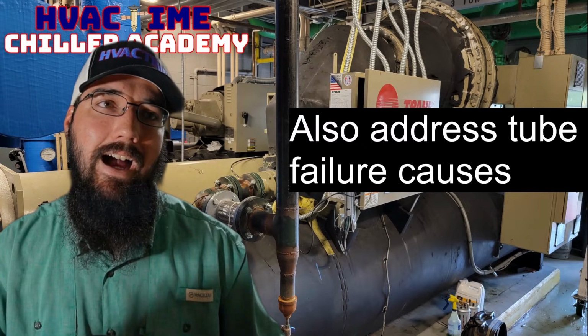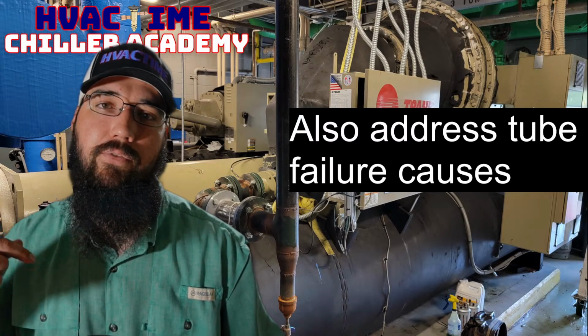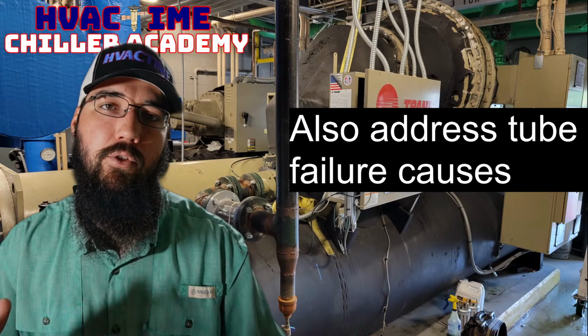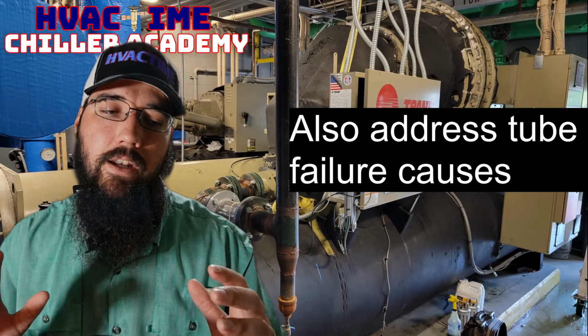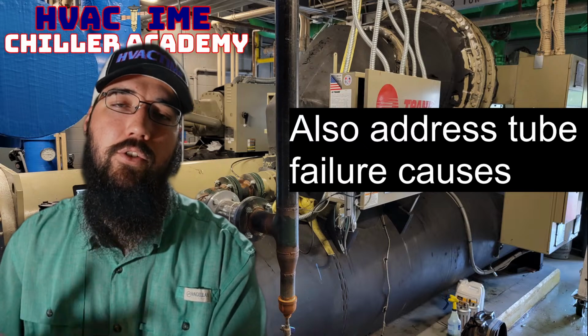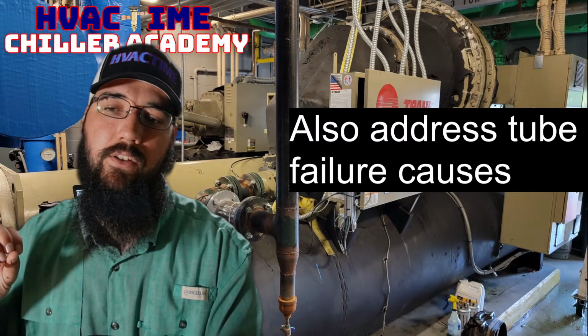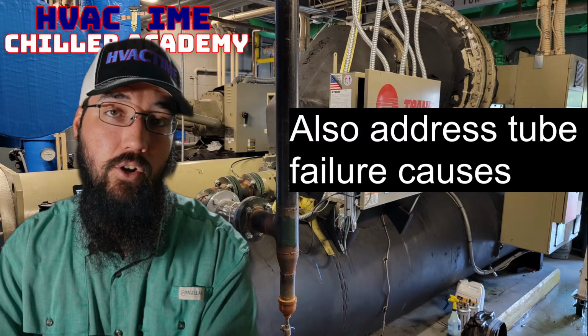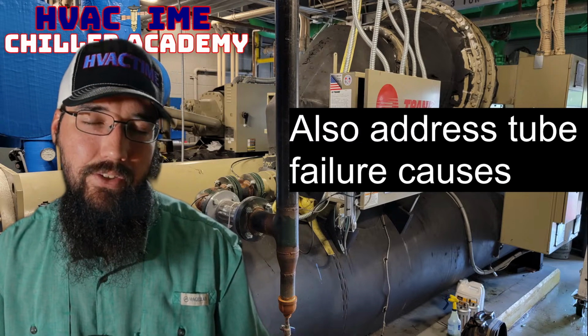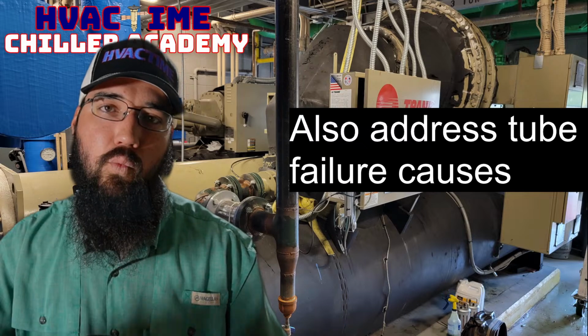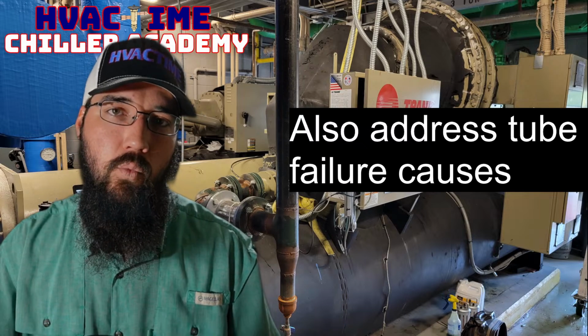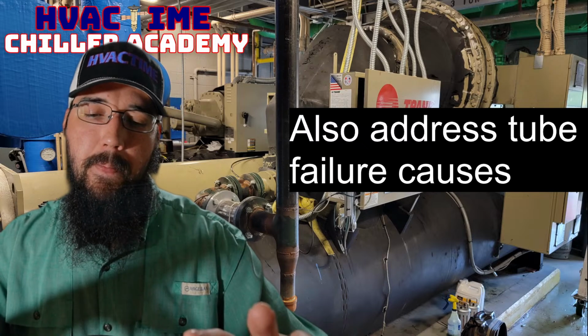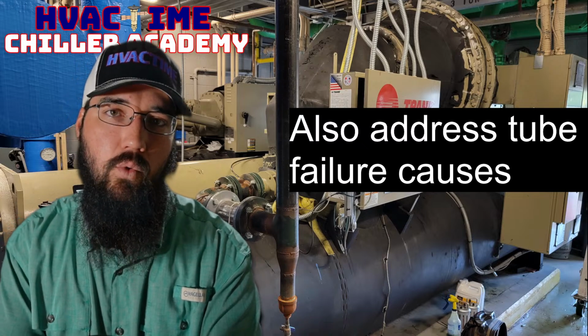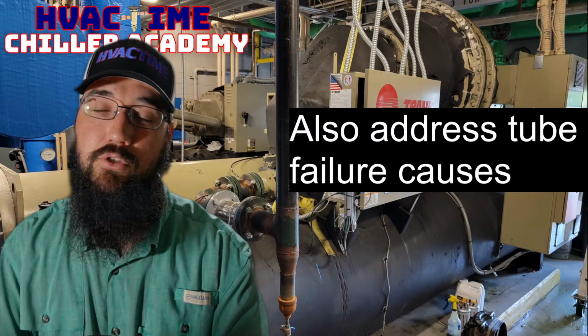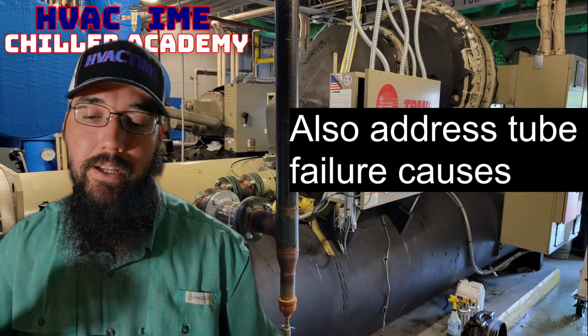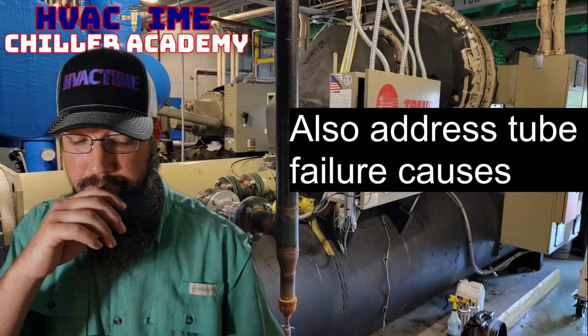So general erosion is one of the methods, and it's more than just contaminants in the water system. Also high GPM. If you're flowing excessive GPM through your heat exchanger, then that extra water flow is going to add additional erosion because it's flowing through there far faster and harder than it technically needs to. And that puts more wear on your tube wall. So erosion is one way. Just straight debris causing a puncture is another.